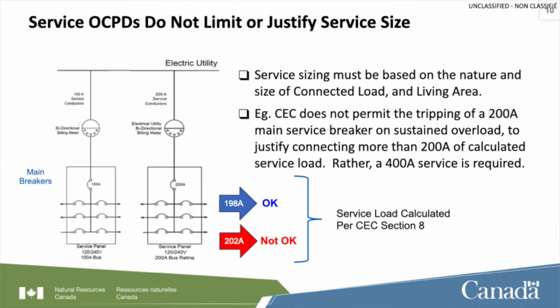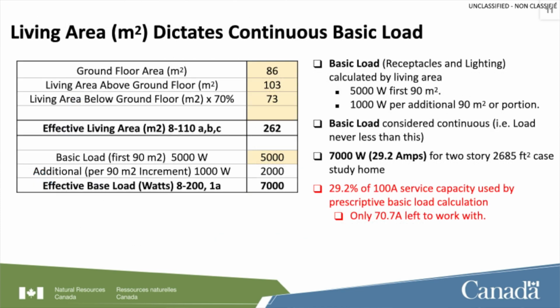Living area dictates our continuous basic load. The first thing we have to do is figure out how much living area we have. In this home we have about 262 square meters altogether. We get 5,000 watts for the first 90 square meters and 1,000 watts for every 90 square meters or portion thereof afterwards. So the effective base load for this home is 7,000 watts, or about 29 and a bit amps - not that bad. We still have a little headroom over our base loads.